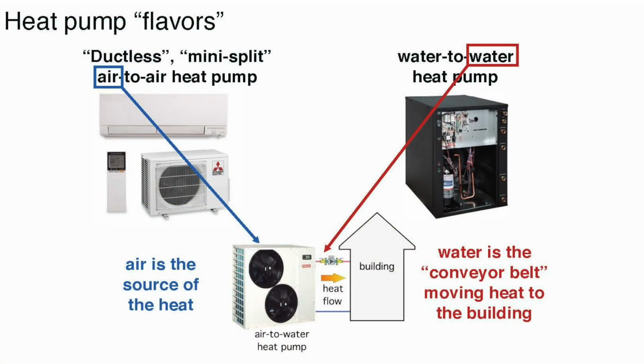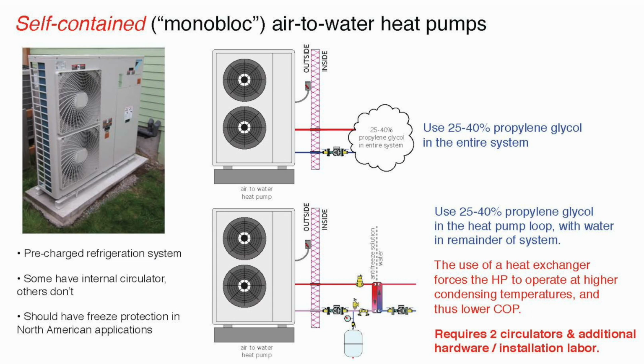So real quickly, what is it? Well, you're all familiar with these air source units, and you're familiar with geothermal, water to water. So all we're doing with an air to water heat pump is we're basically using the air side of heat pump technology for source, and we're using the water side for delivery. Okay?